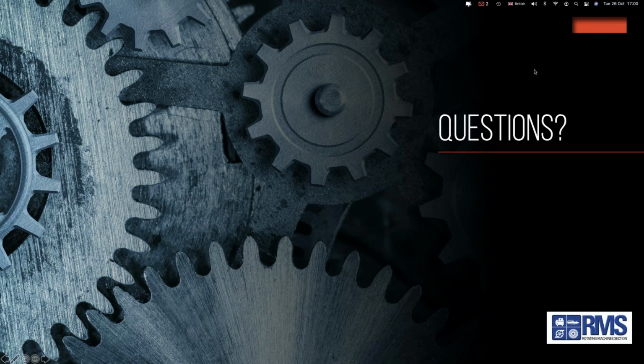Okay, the first question. I actually went on a search about this, and the best guide is an EPRI guide on repair of a range of nuclear motors. It's a very good guide, and it's also publicly available. I'll actually send it to you, Althea. In it, they give guidelines for the recommended range of dielectric stress, and it's between 2 and 3 kV per millimeter. So it doesn't address the specific aspects of the range that I'm talking about. I talk 6.6, but it could just as well be 4.16 kV in the US or 7.2 kV in Europe. I think it's just that range.